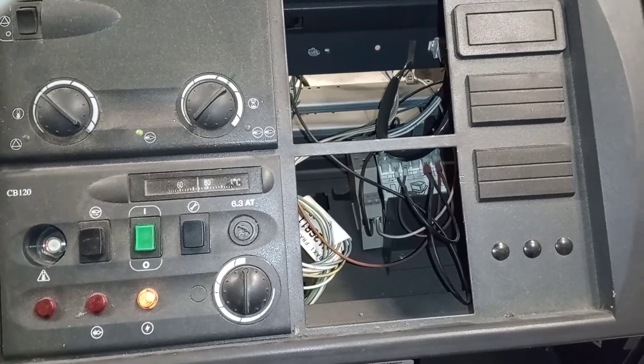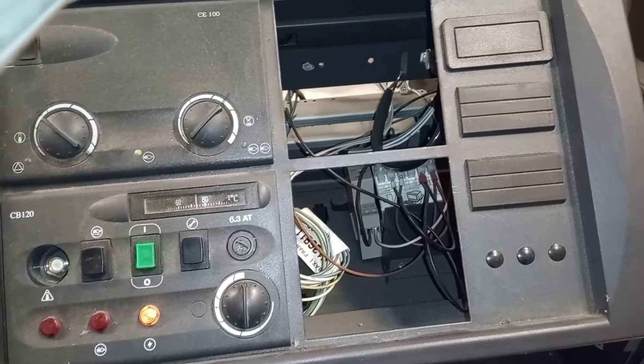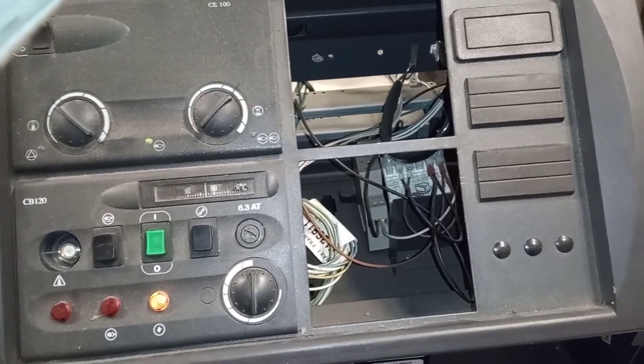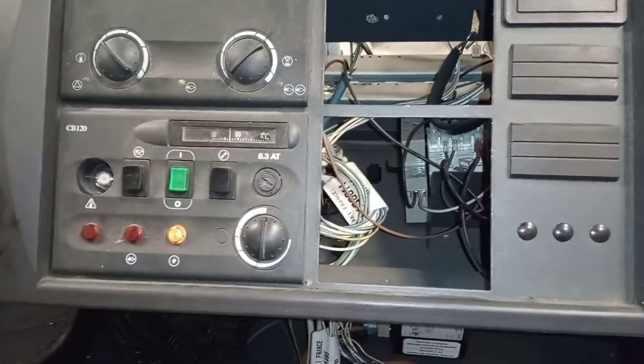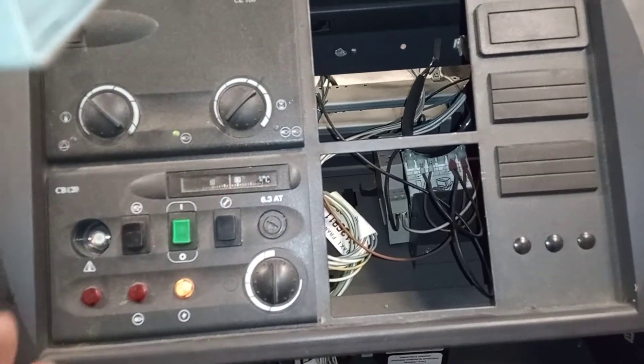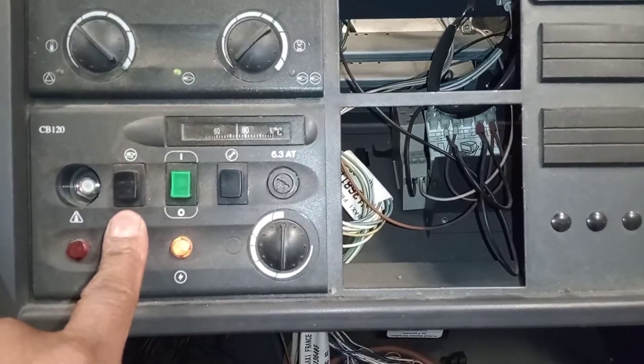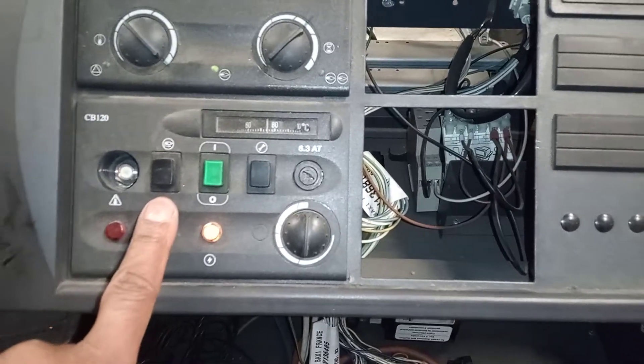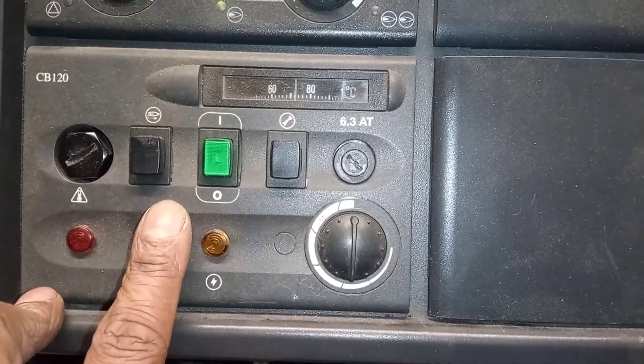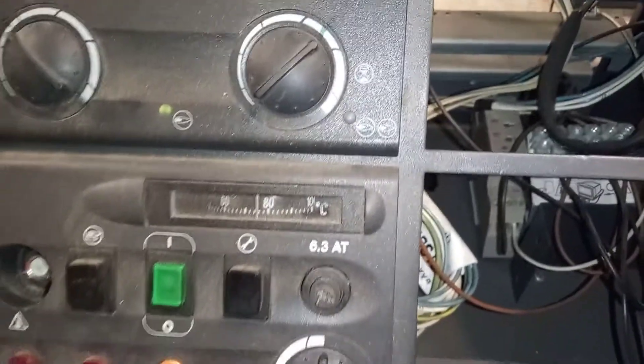Either the electrics have tripped or a smoke alarm test has taken place and the gas solenoid has stopped the gas supply — something to that effect. Before hitting the reset, I made a note of the fault code. Before resetting boilers you should always make a note of what fault you have. I held down the reset for about six seconds and on boiler number one it went through the ignition sequence and started up.